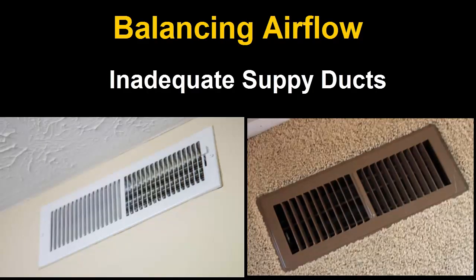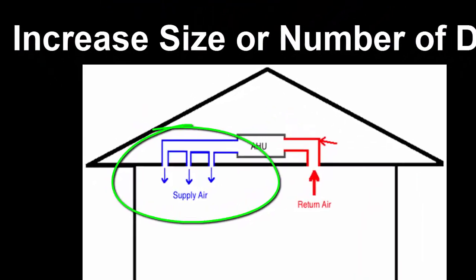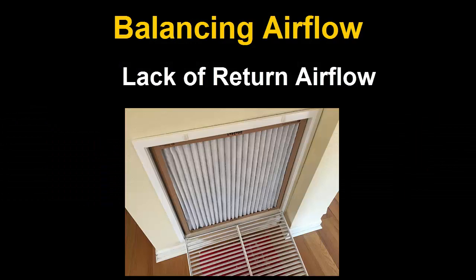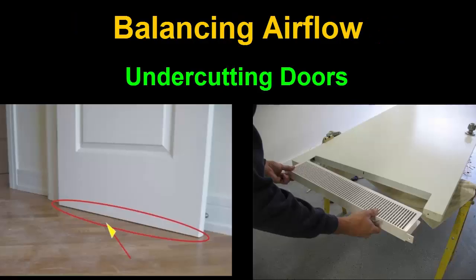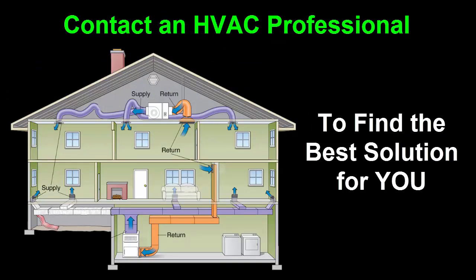Balancing airflow: some rooms may be hard to heat and cool because of inadequate supply ducts or grills. You may need to increase the size of the supply duct or add an additional duct to provide the needed airflow to the room. Any rooms with a lack of sufficient return airflow may benefit from relatively simple upgrades, such as installing a new or larger return air register, undercutting doors for increasing return airflow, or installing a jumper duct to create an airflow connection between rooms. To see which one of these solutions is best for your problem, contact an HVAC professional.